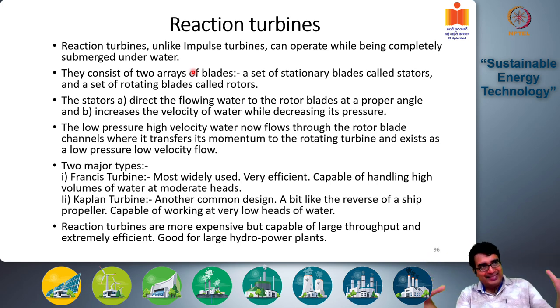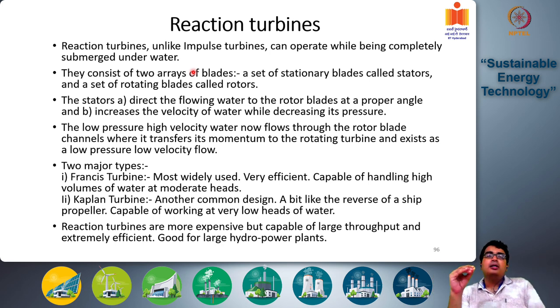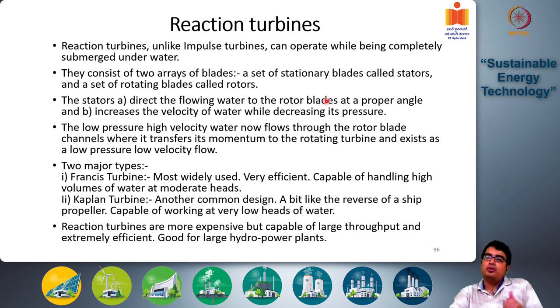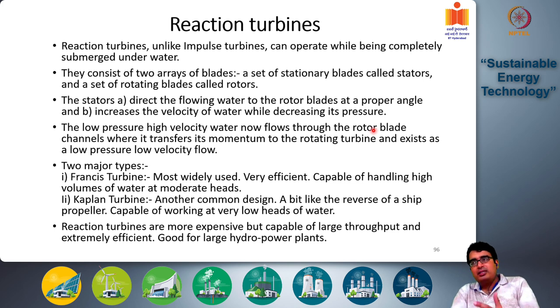The outer blade system is attached to the casing of the turbine and is called a stator because it does not rotate. The function of the stator is directing the flowing water to the rotor blades at a proper angle to maximize the transfer of energy and to increase the velocity of water while decreasing its pressure.